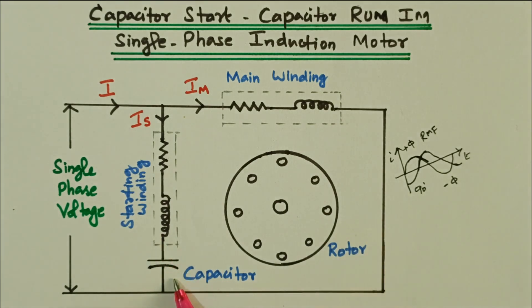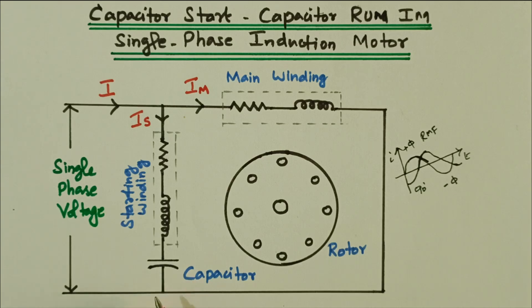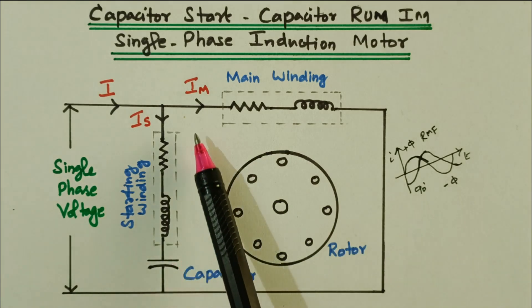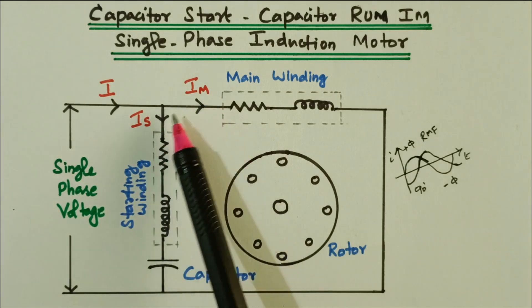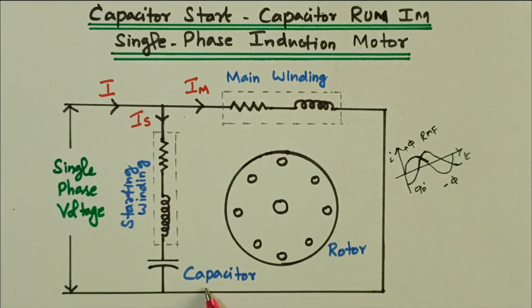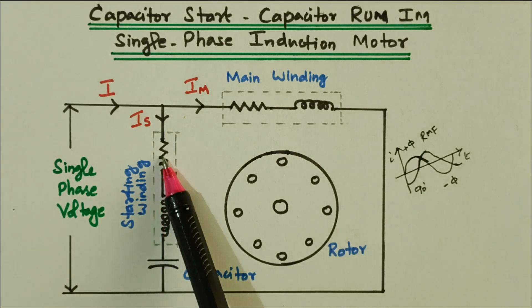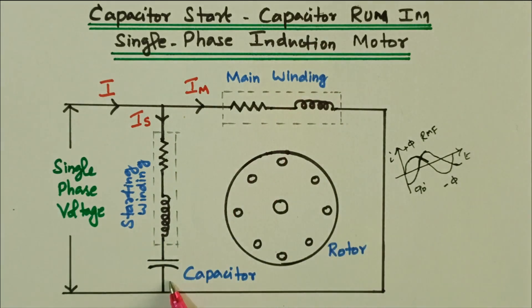To make a phase difference between the currents, a capacitor is connected in series with the starting winding. We know that a capacitor leads the current — the current leads the applied voltage by approximately 90 degrees. There should be a phase difference between the main winding current I_m and starting winding current I_s. Here we are not using a centrifugal switch. The starting winding is used for both starting and running purposes — it is not disconnected, unlike the previous case.